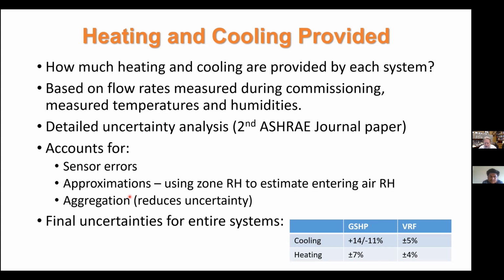It also accounts for aggregation. If you have random errors in different units, but you're measuring, say, 10 units, then that reduces the uncertainty in the total. So the final uncertainties for cooling for the ground source heat pump were about plus or minus, well, 14% on the plus side and 11% on the minus side. For heating, it's about plus or minus 7%. And for the VRF system, the uncertainty is lower, and that's because all the units were running all the time, so we get this aggregation issue that reduces the amount of uncertainty.